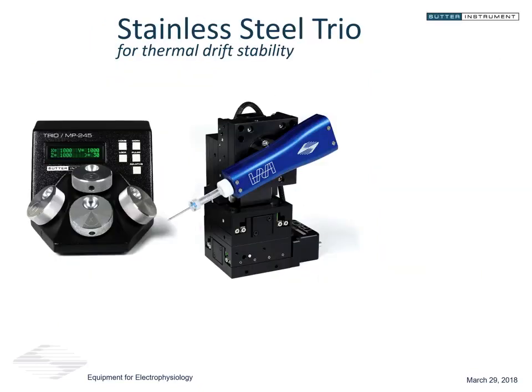Now, thermal drift, and actually pipette drift, is a bit of an issue. When people are designing these components for these systems, particularly the things that hold the pipettes, one of the things that comes into the designer's mind is, how do we make this stable, stable, stable? Well, when a pipette is attached to a cell for quite some time, that pipette may drift, and some of that drift can be due to thermal stability, so thermal expansion. If we look at this manipulator, it's made out of aluminum, and aluminum does have an expansion coefficient.